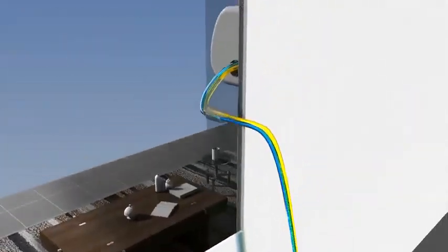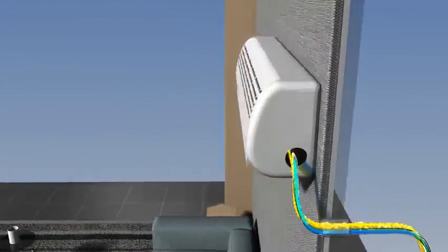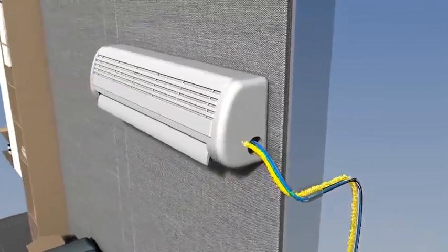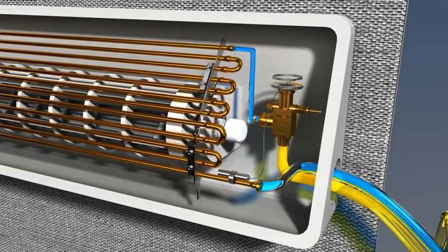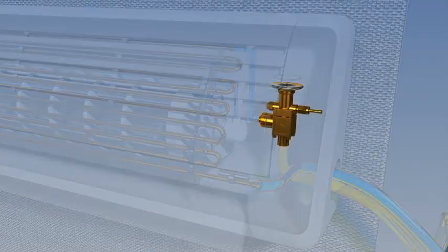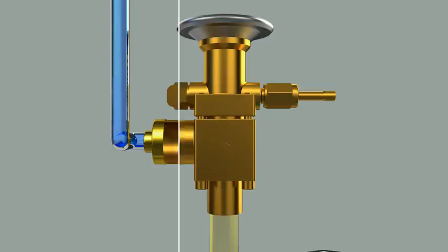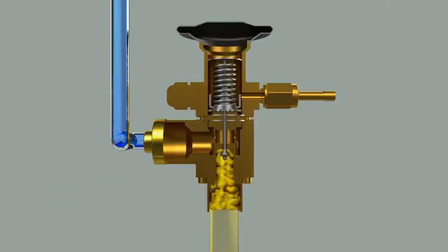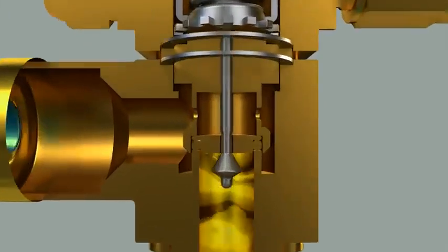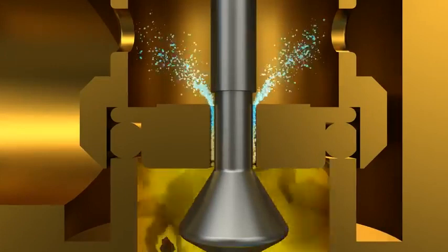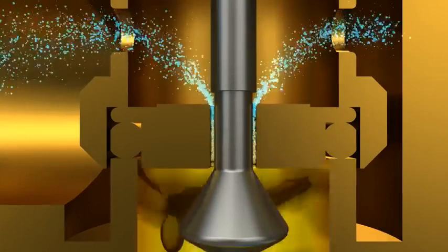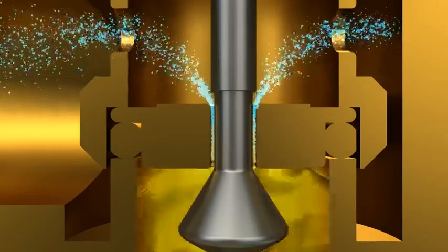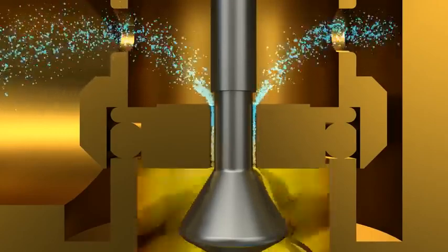Although the refrigerant has thrown off some of the heat as it passes through a condenser, it is still hot, with temperature at about 50 Celsius. The refrigerant in high temperature and high pressure liquid flows into the expansion valve. The refrigerant which used to flow in large space now passes through a narrow area, and its pressure drops as it goes. When the pressure drops, temperature drops dramatically as well. The cool refrigerant is now sent to an evaporator.